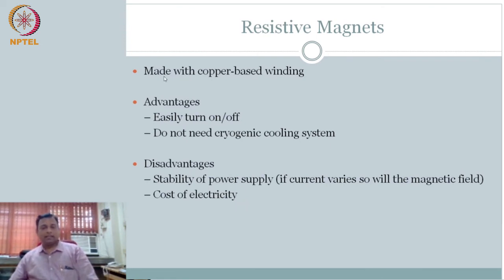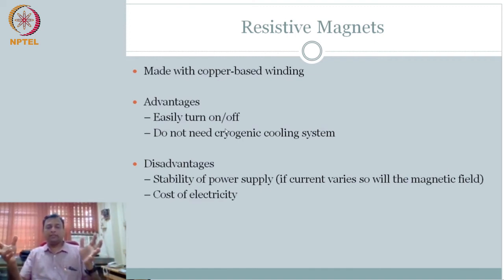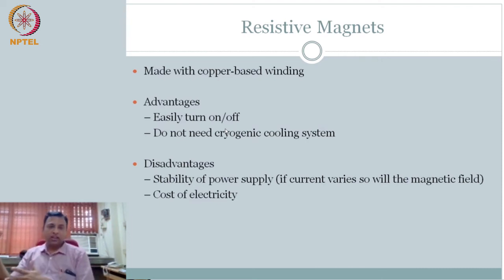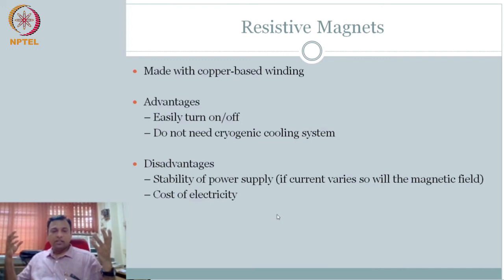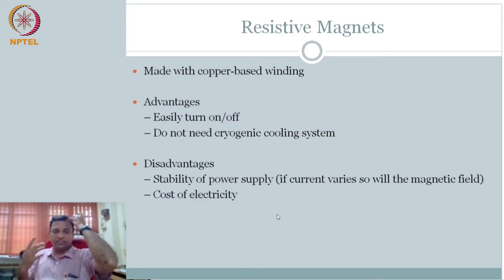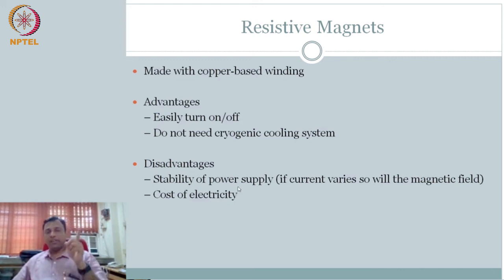Resistive magnets are slightly better than permanent magnets in that you can turn them on and off, and they do not need a special cooling system. However, the key disadvantage is that they run on electricity, and fluctuations in the power supply change the current, which changes the magnetic field — and you do not want the magnetic field strength to change. Also, the achievable Tesla is still only in the fractions. So resistive magnets also have significant limitations.